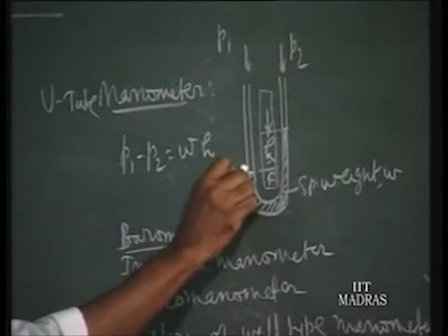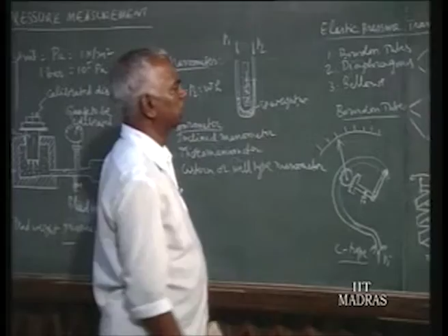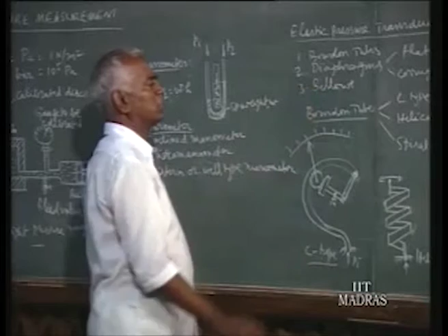So we will go to the other types, which are mainly used for measurement at medium and high pressures. They can be classified under these three groups: Bourdon tubes, diaphragm types, and bellows. These are the three elastic elements. They are made up of materials like phosphor bronze, beryllium copper, and stainless steel, which are used to make the elastic pressure transducers.